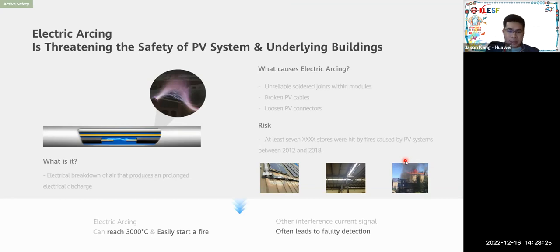But for DC, it's not mature yet, I would say. And for PV systems, it's actually DC powered. So when you have a fault in a DC system, it's a direct current, so where there's a fault, the arc temperature can reach up to 3000 degrees Celsius. And you don't want this to happen, fire incidents, as you can see in the illustration I showed you earlier in the residential scenario.